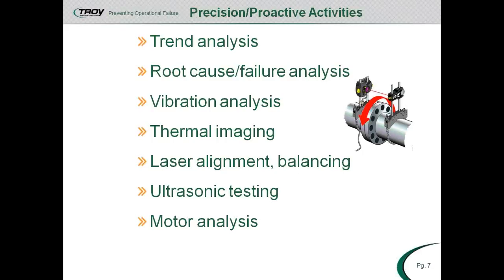With the corona or arcing conditions inside switchgear, there's all sorts of elements that we can use to hear beyond the range of the human ear. The EPA published findings that ultrasonics can save you thousands of dollars by finding lost air. I'm going to give you an example in the EPA published report. A 3/8 inch leak in a year will cost you approximately $3,000 in energy cost by trying to create that type of energy to just basically losing it.